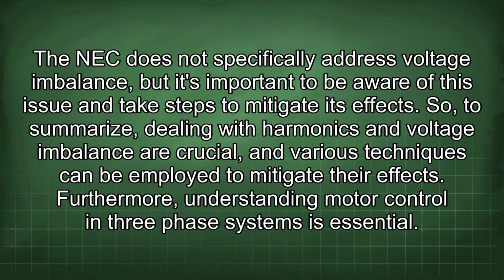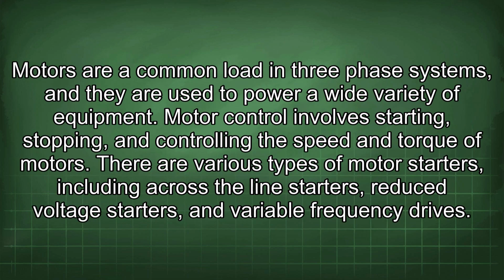Furthermore, understanding motor control in three-phase systems is essential. Motors are common loads in three-phase systems, and they are used to power a wide variety of equipment. Motor control involves starting, stopping, and controlling the speed and torque of motors. There are various types of motor starters, including across-the-line starters, reduced-voltage starters, and variable frequency drives.